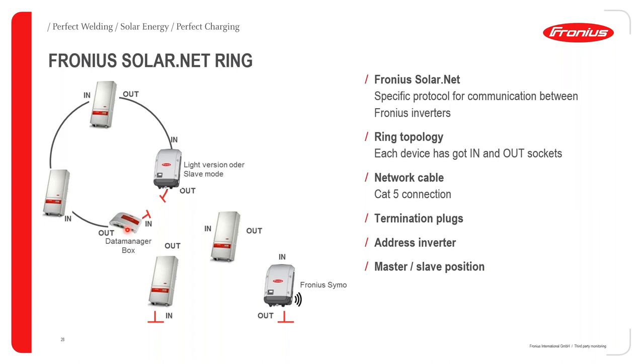For the device with the Data Manager — or Data Manager box — the cable goes out into the next device it's communicating with. From the out port, it goes to the in port of the next, continuing until the last device in the ring. Stop plugs go on the out port and the in port of the device with the Data Manager. Ensure that for the device with the Data Manager, it is in the master position, and all other devices are automatically in slave position.